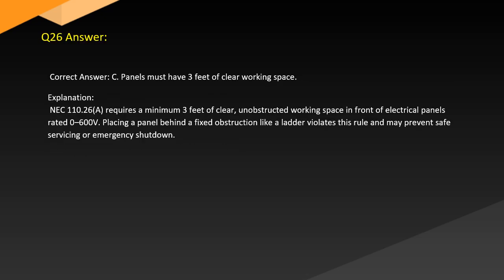Answer. Correct answer: C. Panels must have 3 feet of clear working space. Explanation. NEC 110.26(A) requires a minimum of 3 feet of clear, unobstructed working space in front of electrical panels rated 600 volts or less. Placing a panel behind a fixed obstruction like a ladder violates this rule and may prevent safe servicing or emergency shutdown.